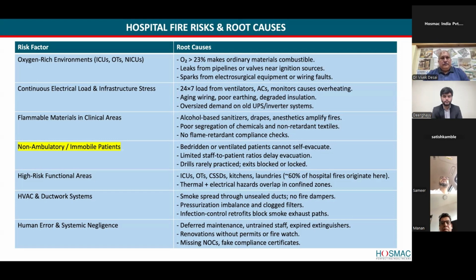Yes, yes. So normally, if you see a large hospital, you will see an AHU system, air handling unit system, consisting of one air handling unit, and then there will be a supply duct and a return duct. So air circulates through a supply duct and returns back to the AHU by means of the return duct. So it goes on in a normal condition, but when a fire happens and smoke gets generated, what happens if the AHU is kept switched on during that period? Then the smoke gets circulated inside all the spaces via the AHU. So one has to put a fire damper in the supply duct as well as the return duct.